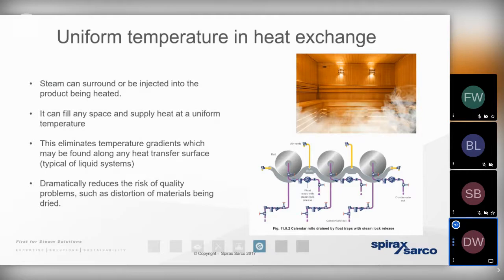Another critical benefit of using steam compared to water as the primary source of heat energy is we need to remember that steam gives up its heat energy by condensing, by changing state from gas to a liquid. And that means that the speed of heat transfer, or the heat transfer coefficient, is about 3 times greater than with a water-to-water heat exchanger. So those 3 benefits help us to understand why we only need a smaller heat transfer solution in order to get the heat energy into the process.